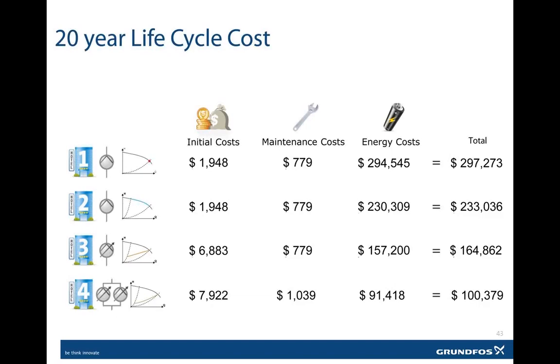Where if we look at the single pump in a variable flow, well then our initial cost and our maintenance costs would be the same, but we would get a reduction in energy costs for when we're operating at the lower flows of $230,309 for a total life cycle cost of $233,036.